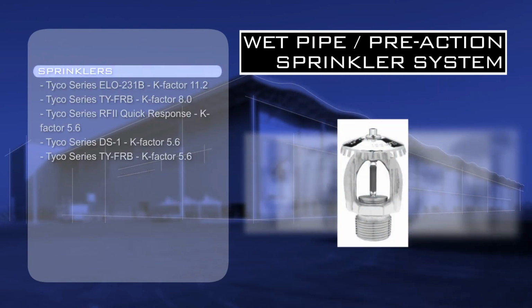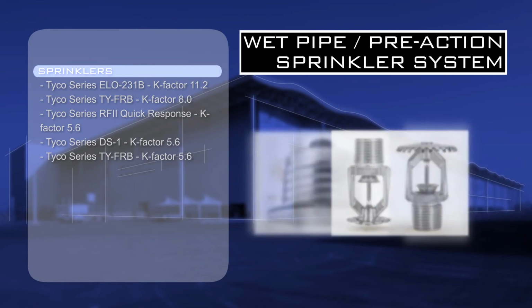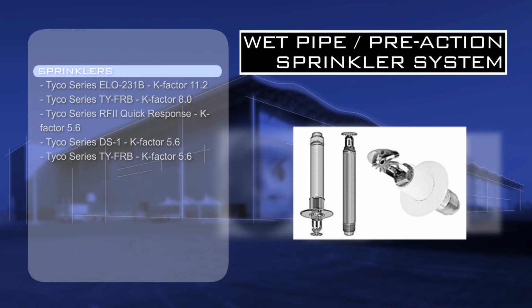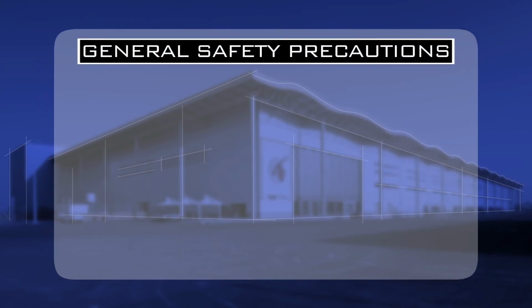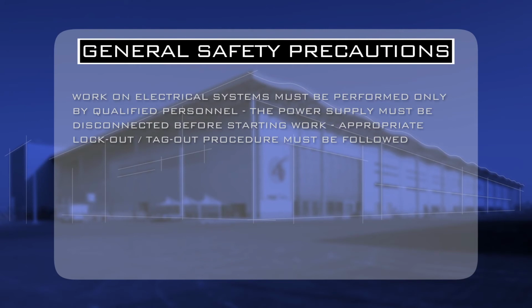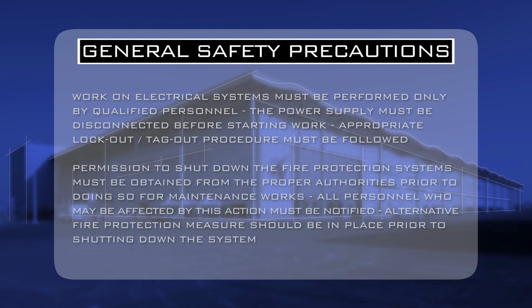There are 5 types of sprinklers in use. There are a number of safety precautions to adhere to. Work on electrical systems must only be performed by qualified personnel. The power supply must be disconnected before starting work, and the appropriate lockout or tagout procedure must be followed. Permission to shut down the fire protection system must be obtained from the proper authorities before doing so for maintenance work. All personnel who may be affected by this action must be informed, and alternative fire protection measures must be in place before shutting the system down.